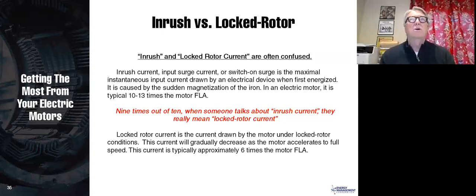And then the locked rotor current will gradually diminish as the motor comes up to speed and as the slip on the rotor gets lower and lower. So, as I say, I don't get too worked up on this, but whenever people talk about inrush, I always listen carefully, because 9 times out of 10, what they actually mean is locked rotor current, not inrush. But inrush can be a very important factor, because inrush can trip a circuit breaker, it can blow a fuse, and your overcurrent protection has to be able to accommodate, say, up to 13 times current for half a cycle in order to not blow.